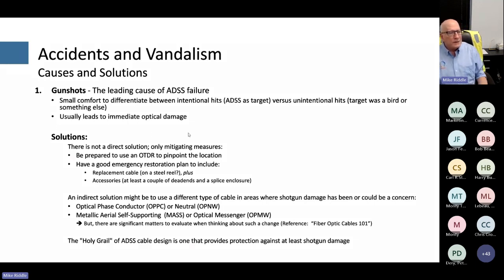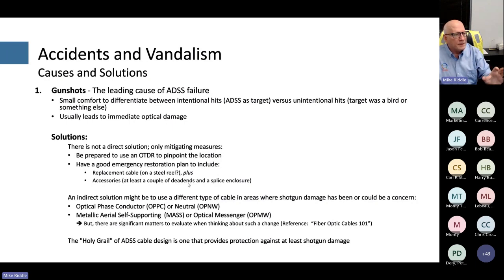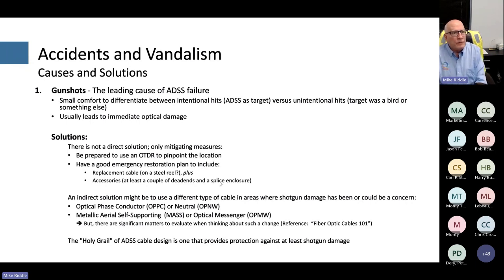There is really no direct solution for gunshot damage. The main thing is to be prepared: have an emergency response plan where you know where the OTDR is to pinpoint the location, and have spare cable, hardware, dead ends, and a splice enclosure so you can quickly get back in service. If it's a repeated problem in the same location, consider using a different type of cable.